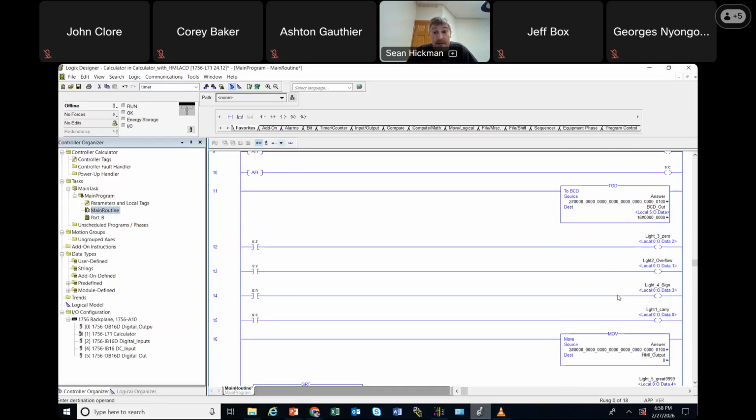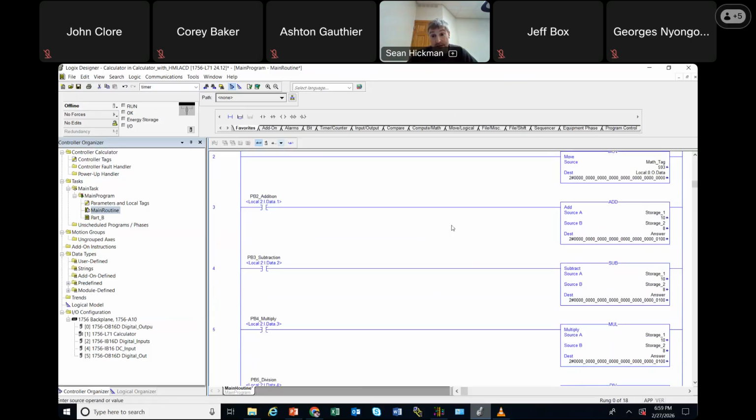The HMI, the beauty of it, just move it. You want to move it, add it, subtract it, compare it. It's just a tag name. Whatever the HMI brings in as a DINT, if it brings in 375, bang, that's your tag. You don't have to do any of this stuff to it. So don't be trying to TOD an HMI value that you brought right in as a DINT, because you bring 375 in, you get 375, and you are in business. All right. The TOD and the FRD is for the thumb wheel, and we're just doing that to show you how it's going.